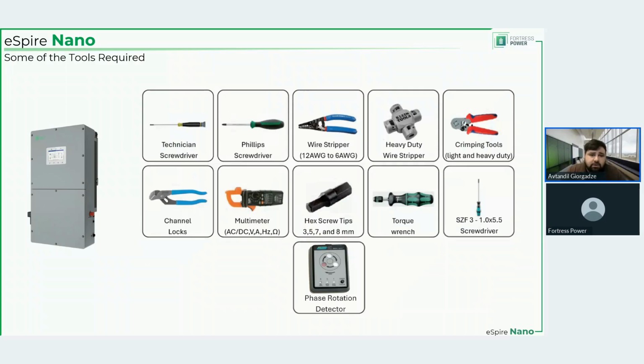Now let's look at some of the tools that we might need in the field. Screwdrivers, wire stripper, crimping tool, channel lock, multimeter, hex screw tips, torque wrench, all the things that we are really used to seeing in the field. But for those that have not worked a lot on three-phase systems, the last one here, the phase rotation detector, could be a new item that they have not necessarily used in residential, because in residential, you are working with one phase, which is split into two. So that 240 is one phase, and you have 120 to neutral, that's your L1, and 120 to neutral, that's your L2.